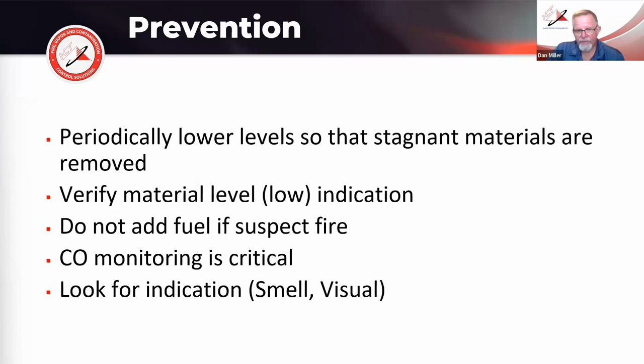This shows carbon monoxide monitoring as being a great early fire detection method for use in coal bunkers. It's really a necessary method. As coal begins to combust, it gets up around the 200-degree level, and you start to experience a rise in carbon monoxide. That carbon monoxide indication is very important.